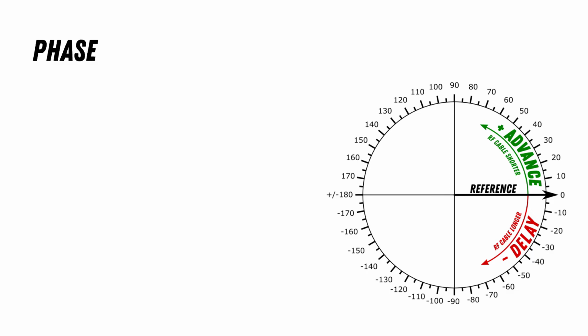So later in this video, I'm going to be measuring a 90-degree cable. But before we measure our device under test, we'll take a 0 reference. So they'll be reading 0 on the phase trace. Once we insert that device under test, or 90-degree cable, we'll see a new phase reading show up of around -90, indicating that this vector, or that wavelength, is now delayed. And so what this vector diagram is trying to show you is that anytime you add cable after a 0 reference, you will move around this vector diagram in a clockwise direction.